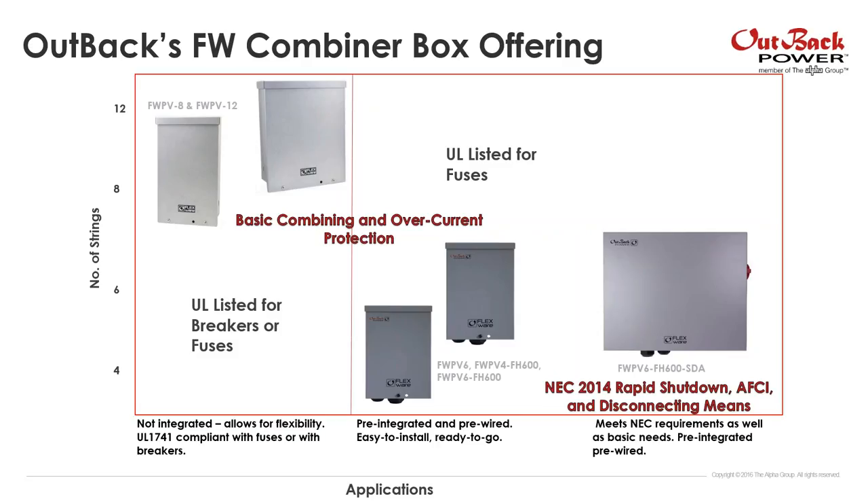Over on the right, we have our integrated combiner solution — that's our NEC solution we'll be talking about today. Our older combiner boxes, the FWPV-8 and FWPV-12, are UL listed for breakers and fuses. However, due to new regulatory requirements, our newer combiner boxes are only listed for fuses because fuses provide bidirectional overcurrent protection.